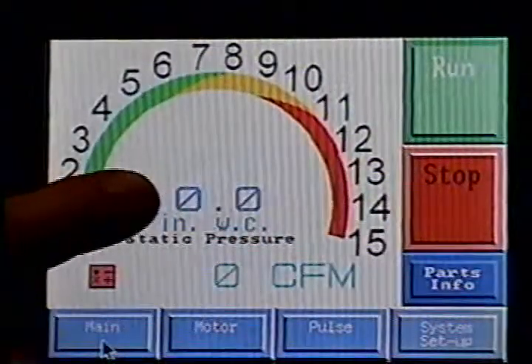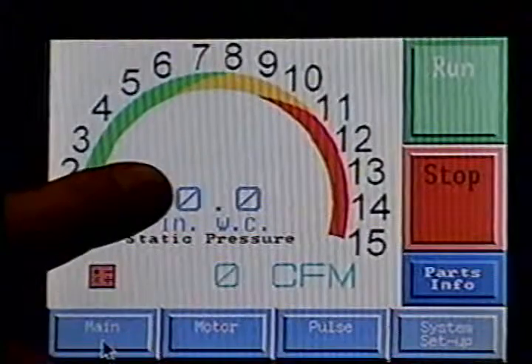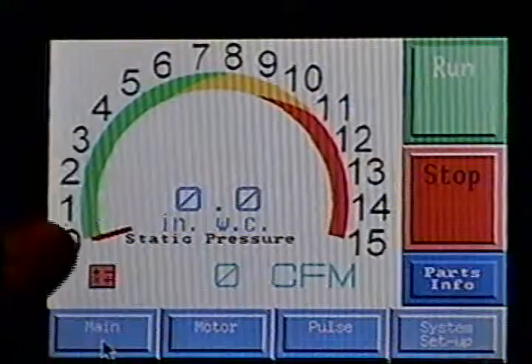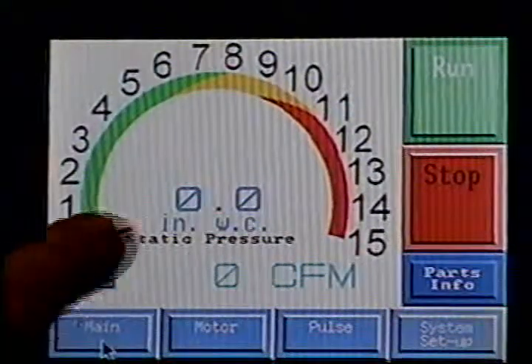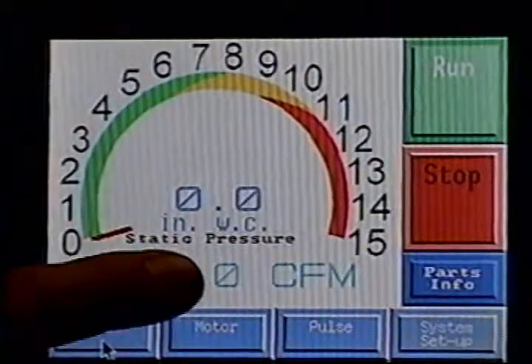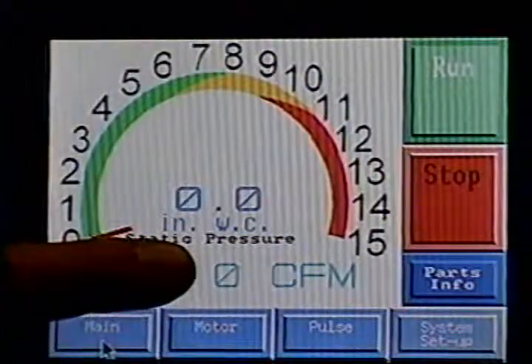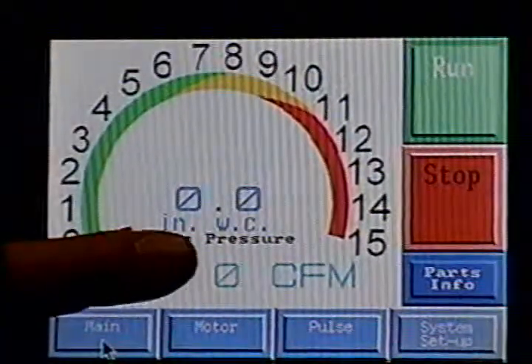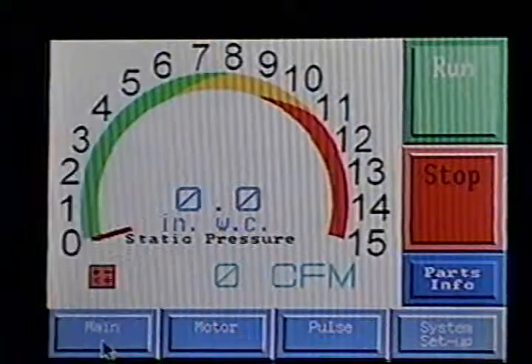gauge would. In addition to that, we offer a digital display of what the static pressure is across the filters. It's labeled inches water column static pressure, and down below that you'll see where it says 0 CFM. That's where you'll actually see a real-time CFM reading for the collector.